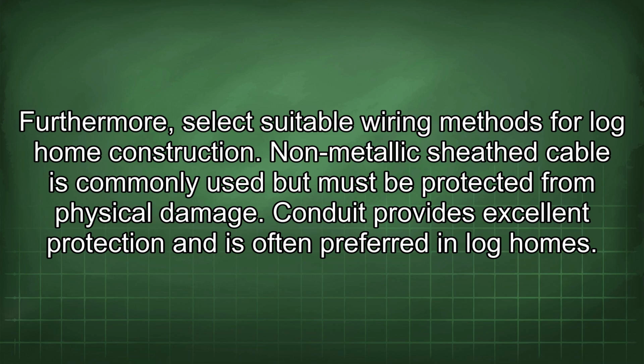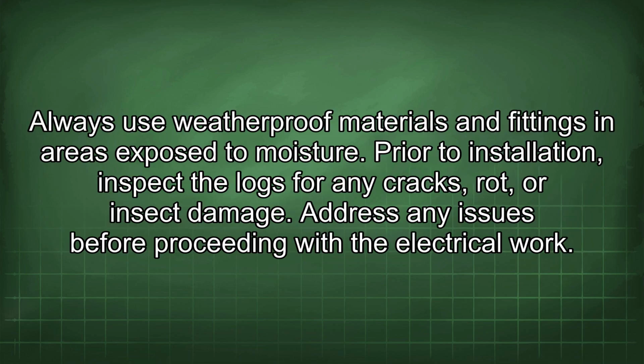Non-metallic sheathed cable is commonly used, but must be protected from physical damage. Conduit provides excellent protection and is often preferred in log homes. Always use weatherproof materials and fittings in areas exposed to moisture. Prior to installation, inspect the logs for any cracks, rot, or insect damage. Address any issues before proceeding with the electrical work.